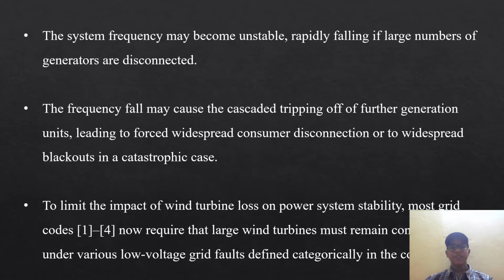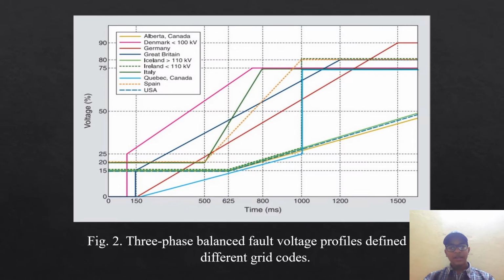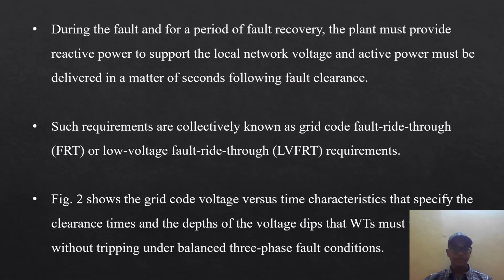The system frequency may become unstable, rapidly falling if large numbers of generators are disconnected. The frequency fall may cause the cascaded tripping of further generation units, leading to forced widespread consumer disconnection and widespread blackouts in a catastrophic failure. And here is a graph of three-phase balanced fault voltage profiles defined in different grid codes.